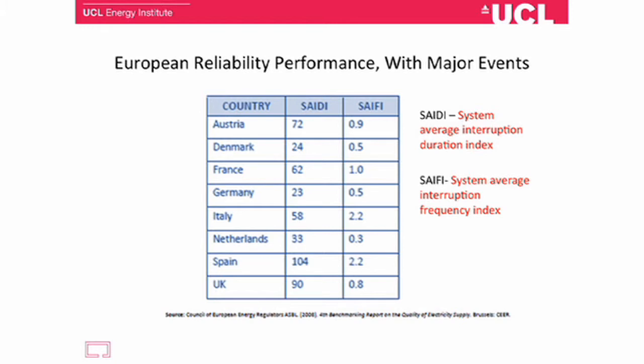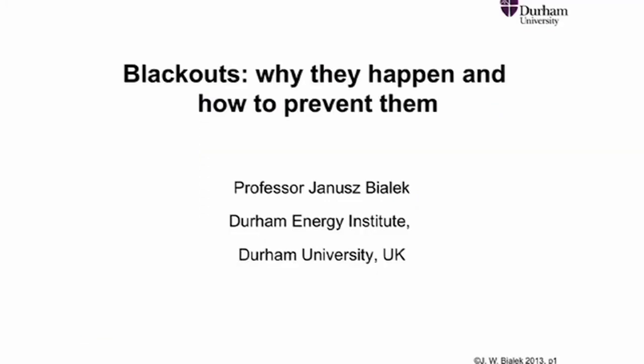One problem in reporting this average data for a state or even for a utility is that it does not address whether the served area is urban or rural. For instance, a utility may have an average interruption duration index of 2 and can have 25% of its customers in an urban area with a system average interruption frequency index of 0.2. Downtown areas tend to be wired with underground spot networks, which are more reliable and costly than radial overhead networks, which can be found in suburban and rural areas.